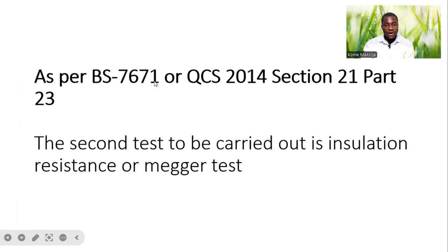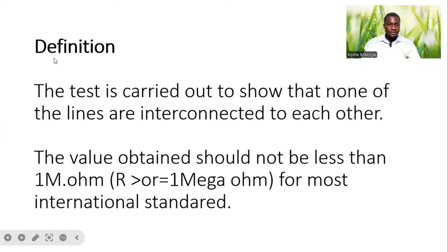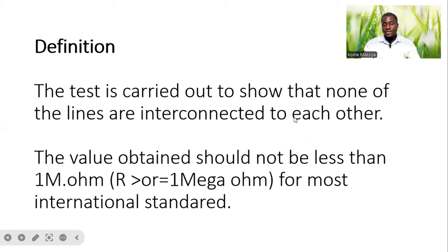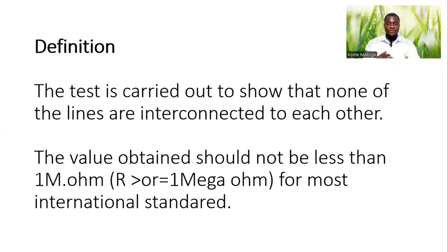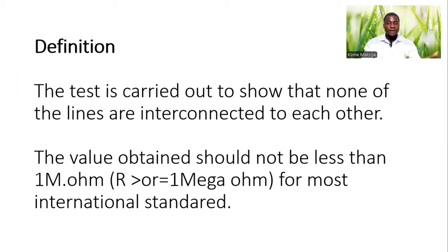Insulation resistance test. We will be referencing BS 7671 or QCS 2014 section 21 part 23. This is the second test that should be carried out as per code. The test is carried out to ensure that none of the lines are interconnected to each other. So if we have different wires that have been pulled on site — phase, neutral, and earth — we have to ensure that we conduct this test to verify there is no interconnection between the different cables.